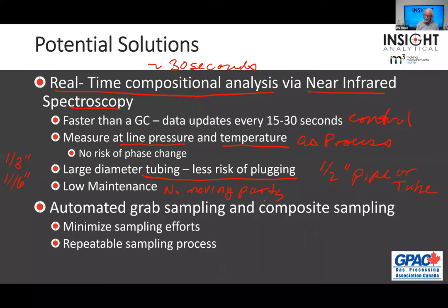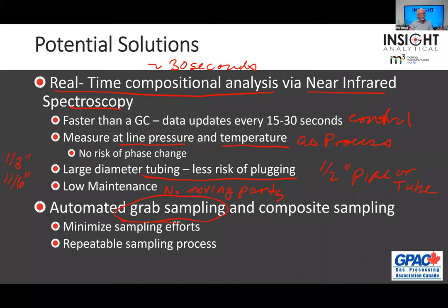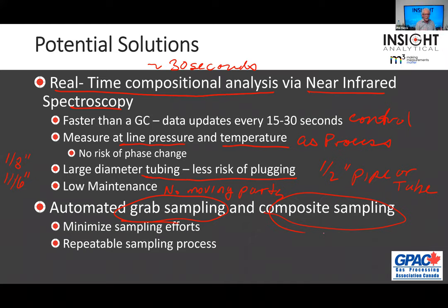We may want to add automated grab sampling. In a custody transfer agreement, nobody believes each other's analyzer. If Gary's selling me condensate and his analyzer says he's on spec — well, when you have one analyzer, you have a measurement; when you have two analyzers, you have an argument. Somebody has to settle the argument, and it's always the lab. So you need a way to get a sample. Whenever you think you've got off-spec product, you want to pull a sample right then. Automated sampling can help grab a sample when you want it, and composite sampling gives you the long-term average. Done well, we can minimize sampling efforts and build a very repeatable sampling process.